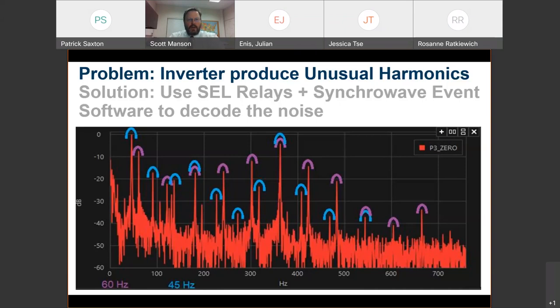Well, it turns out that through a series of event report collections from a relay, we performed a harmonic analysis in SEL Synchrowave Event software, one of our software packages, and we decoded what was happening on the power system. These are tools available in many cases for free, and they certainly come naturally with the relay. So here you see we've decoded that the little blue hats are the harmonic content coming from the engine itself, the reciprocating piston engine. You know, pistons go bang one at a time and they create harmonics. And here they are on the power system. Here in purple, you see the harmonics associated with the interwinding of a small, very simple generator.